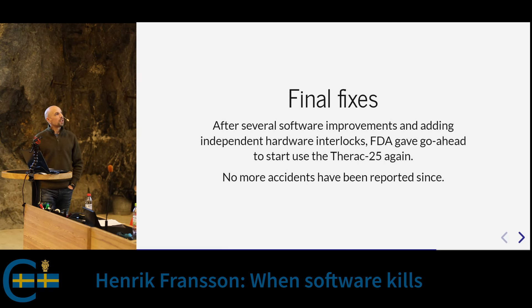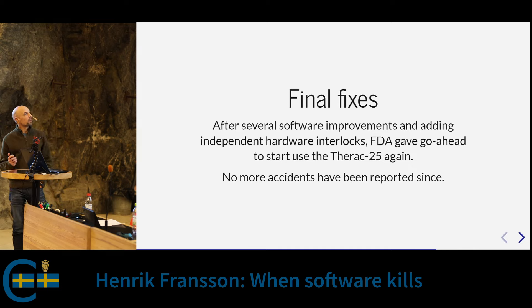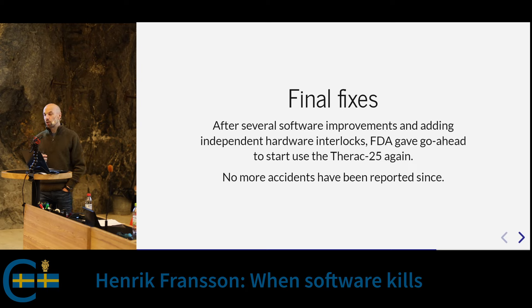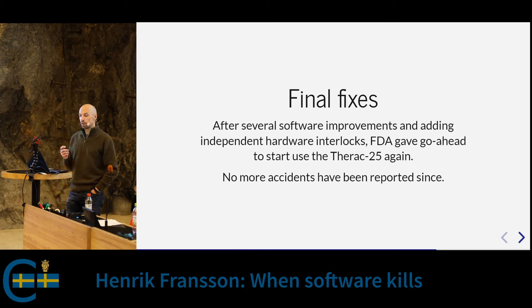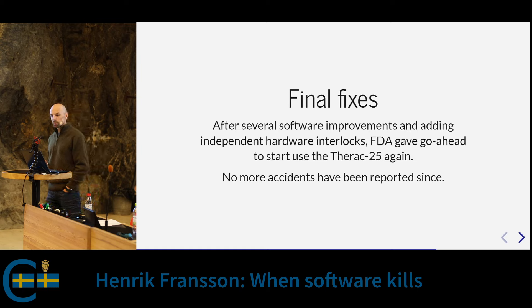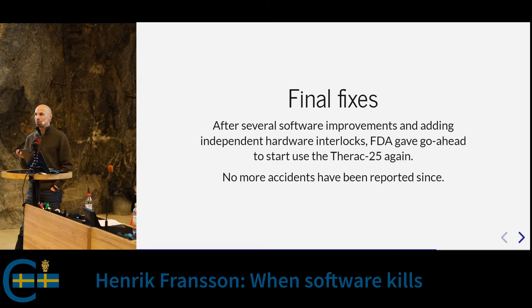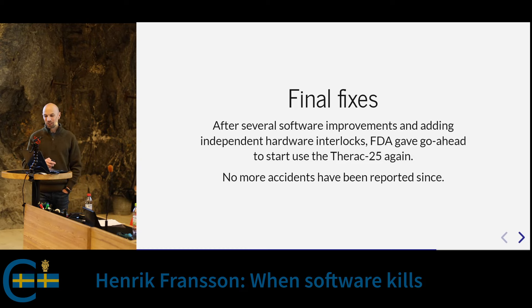Eventually the FDA forced them to make so many changes that they finally applied all the fixes, including all the missing hardware interlocks and redundancy. After that, no accidents occurred — as far as we know. To be fair, these machines probably saved more lives than they took, but you still shouldn't go to a hospital and be killed by it.